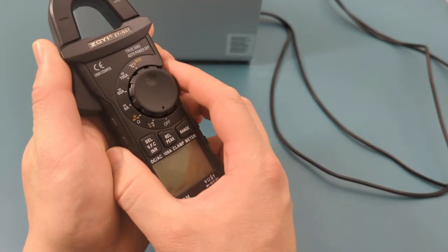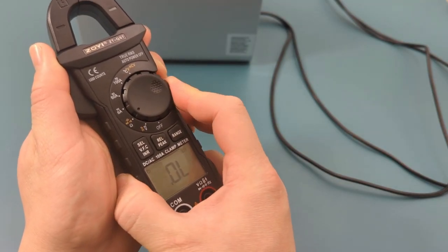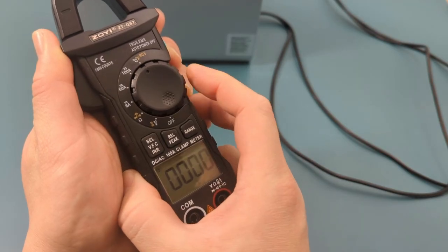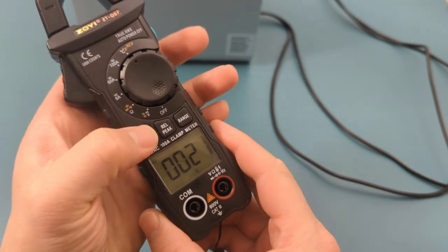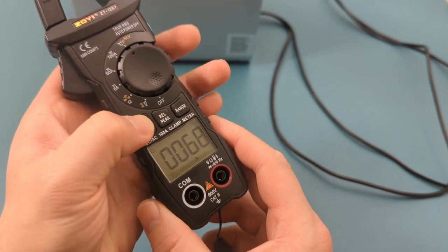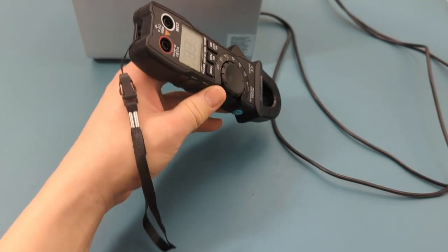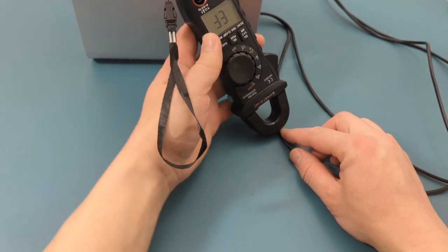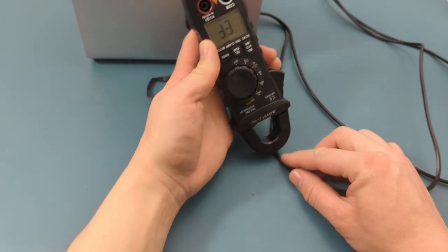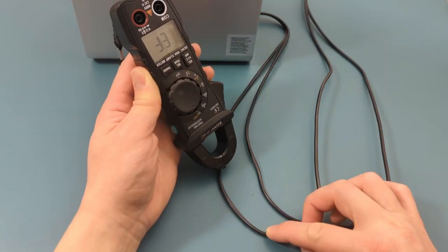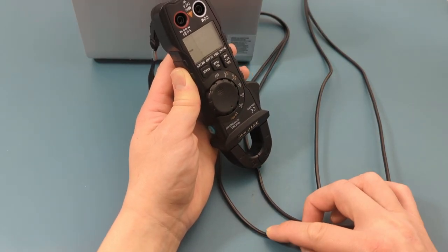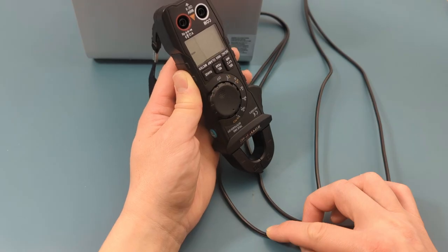The next test involves performing non-contact voltage detection. Turn the dial to the temperature NCV setting. Press the select button to toggle to the NCV mode. The sensor is at the tip of the meter. You will hear a beep sound if the sensor detects an AC electromagnetic field. There is no electromagnetic field because this is the neutral wire. You hear a beep since there is an electromagnetic field, and this is the live wire.